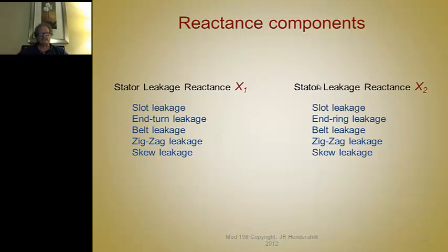And that's made up of several terms. The total reactance is made up of several terms: slot leakage, end ring leakage, belt leakage, zigzag leakage, and skew leakage. In stators, there's very seldom any skew, but there can be.